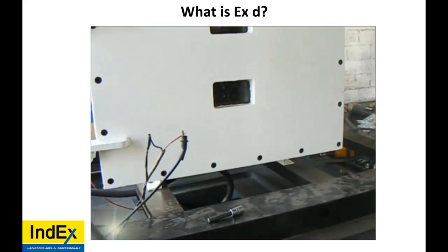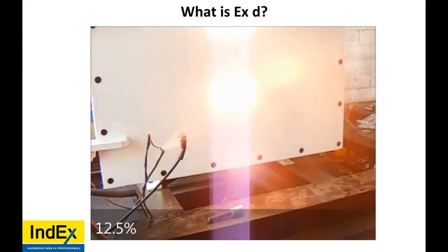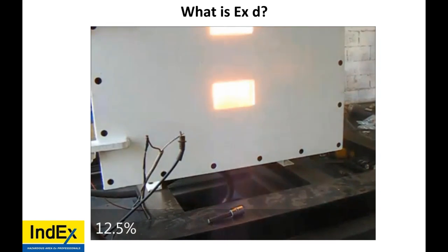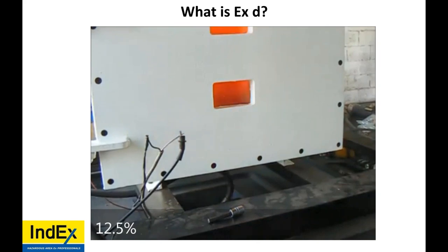So it's important to maintain its protection technique. Have all the bolts in, use the proper glands with the proper cable, or use barrier glands, and use high quality cable. If your cable is not circular and compact, this could happen.